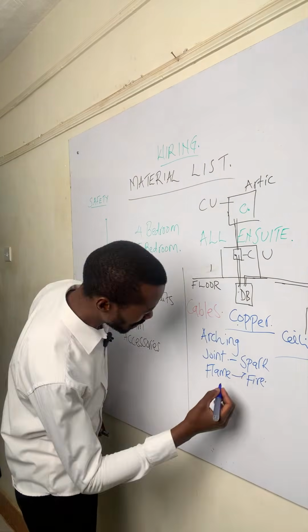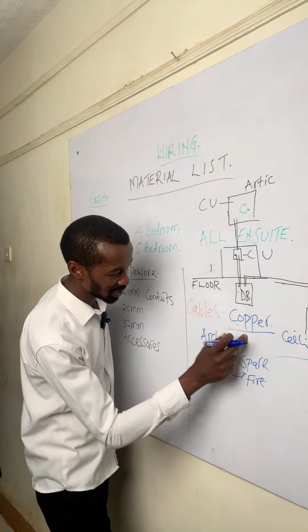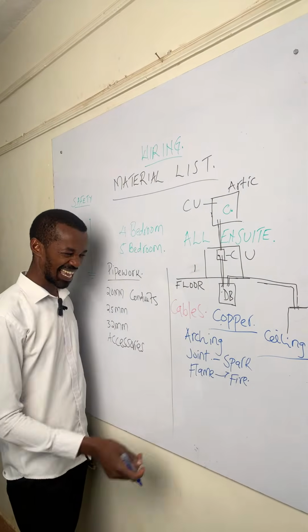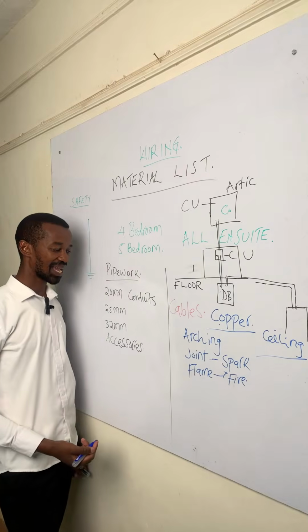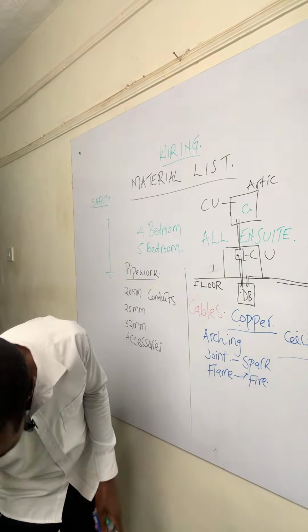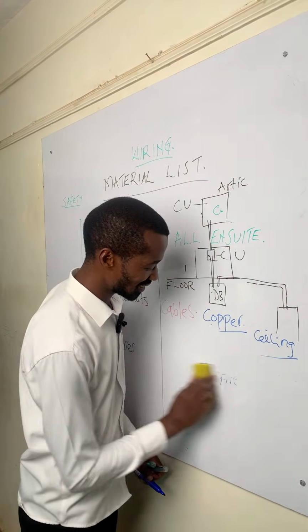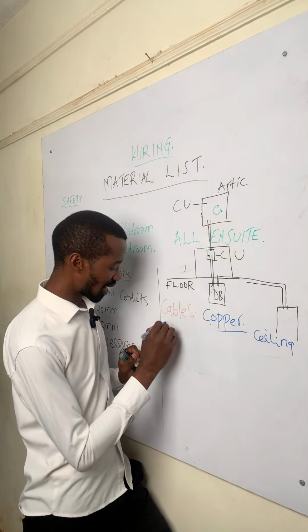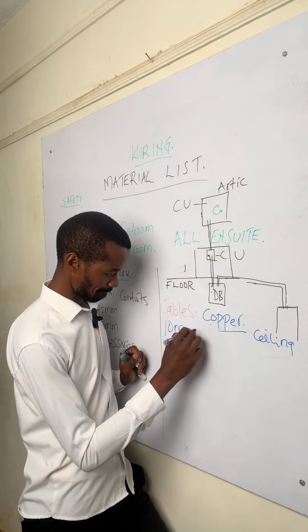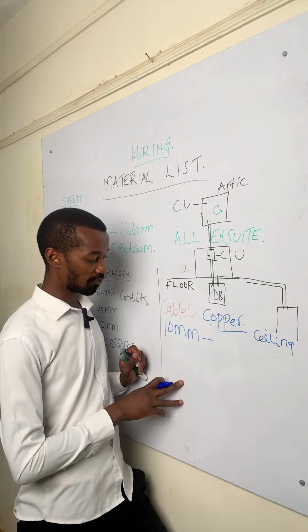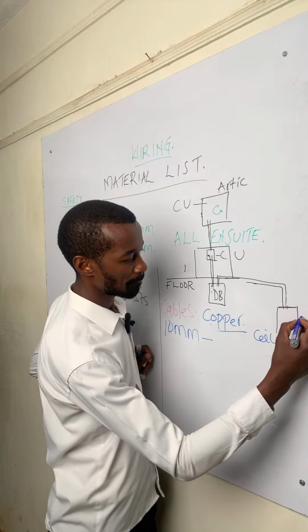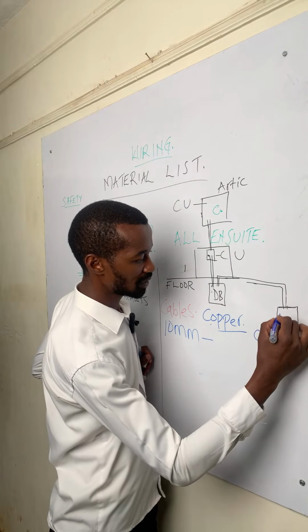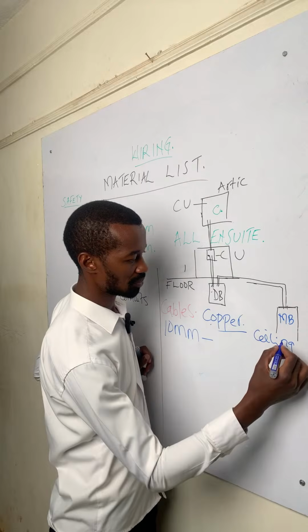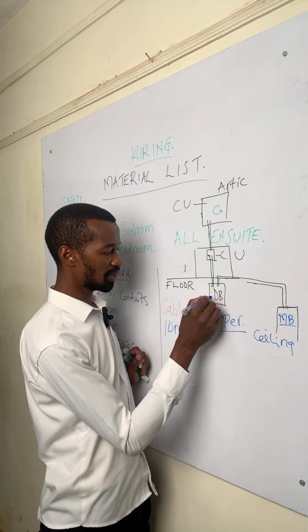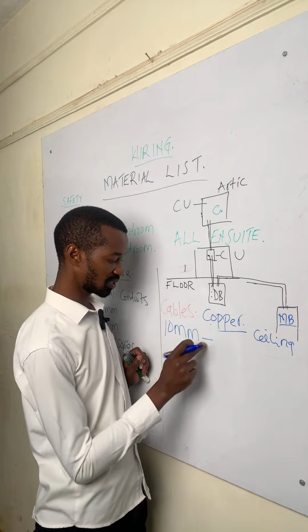Now moving on, we've agreed that when it comes to cables, the material matters, and the size of the cable matters too. Let me go into detail on sizing. We agreed that 10mm is the size for the mains coming from the meter board to the main distribution board. So this is a 10mm cable.